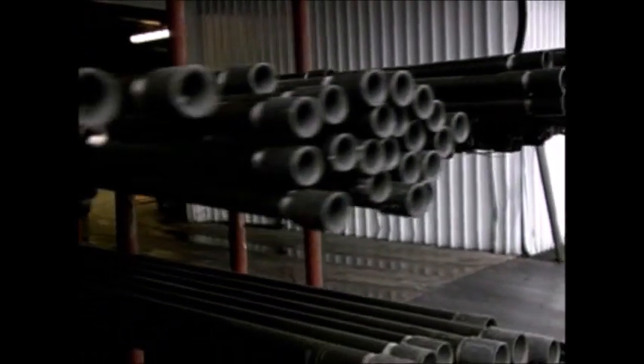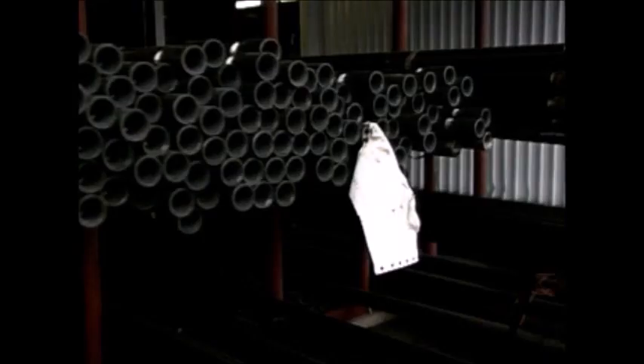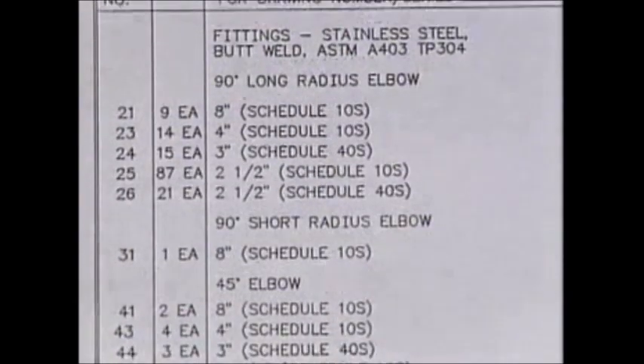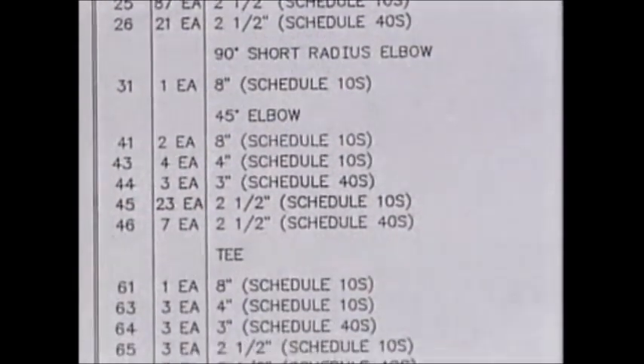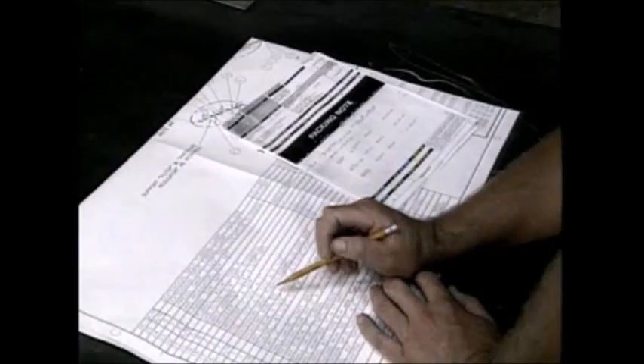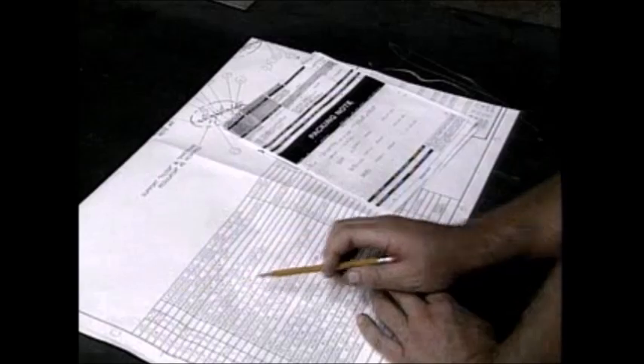Different types of piping look different, but positive identification of piping material should never be based on appearance alone. Piping is identified by ink stamping, or for smaller pipe, by a tag attached to bundles. The identification includes the pipe size, wall thickness, weight per foot, length, specification and grade, manufacturer's name, and method of manufacture — for example, seamless or welded. Always check this information to verify you are using the material called for in the work order or job description.